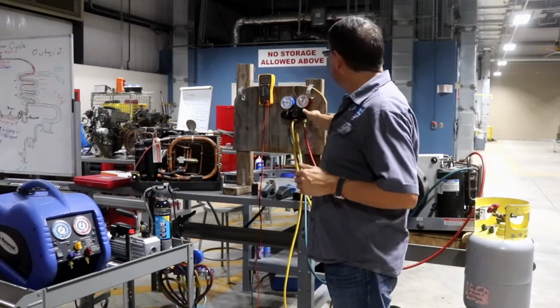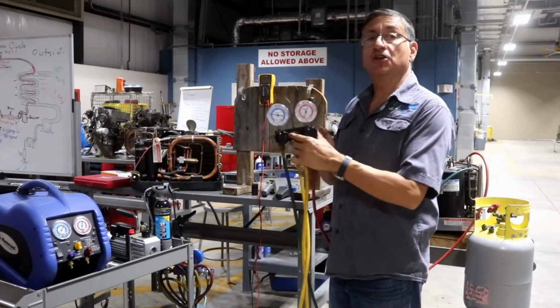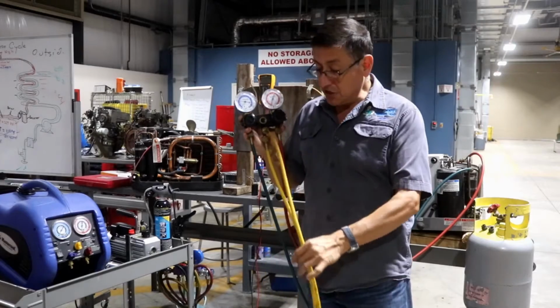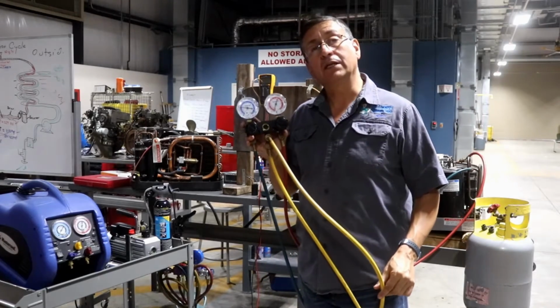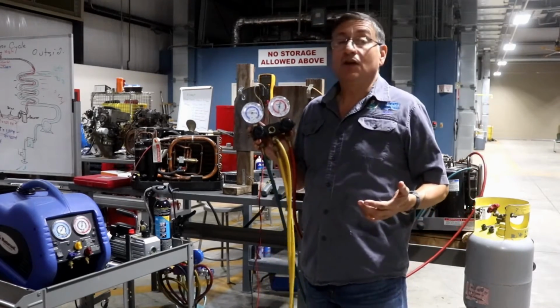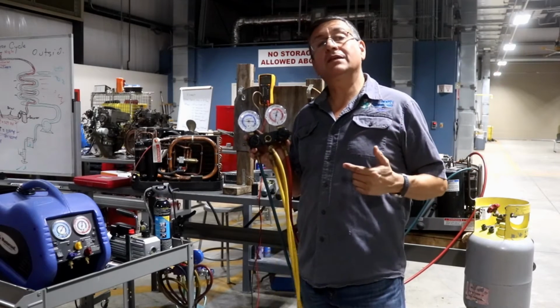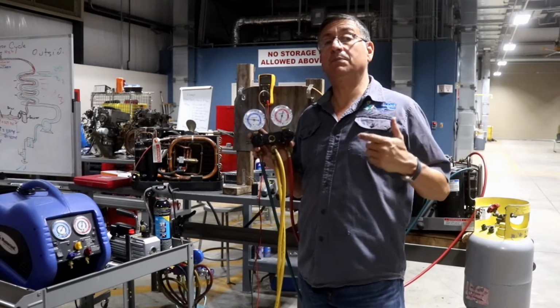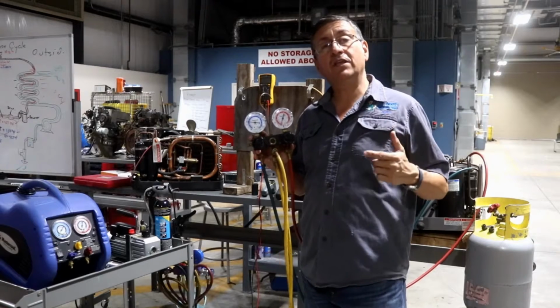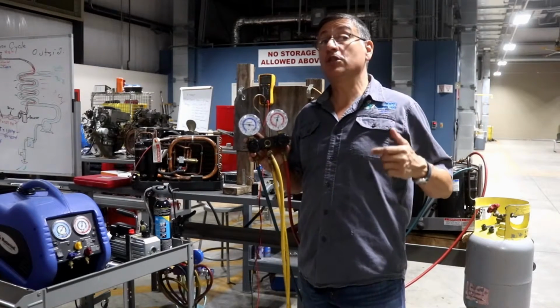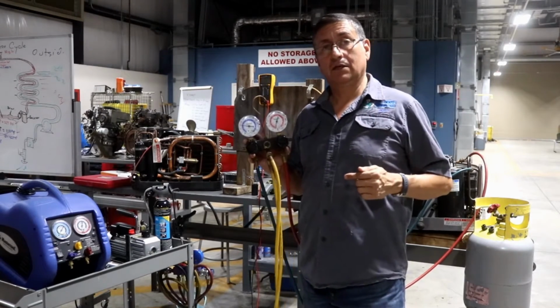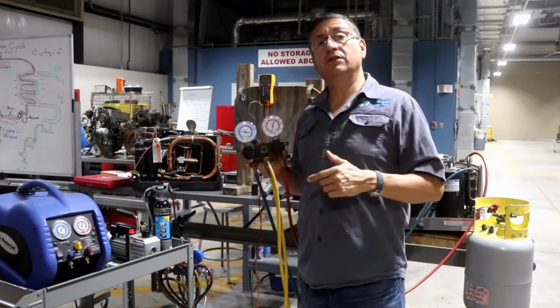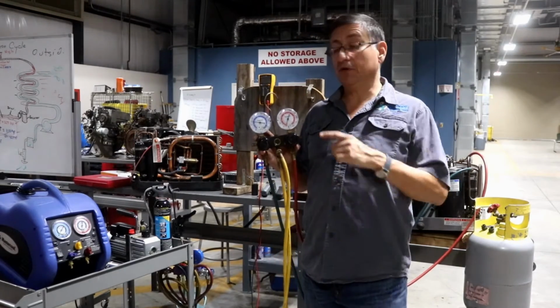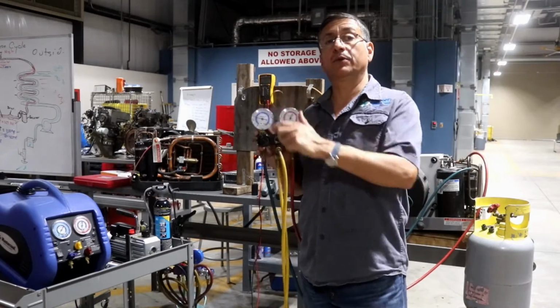One of them is the set of gauges. The set of gauges is very, very important because with the gauges we know the pressure in the system. Remember, in a previous episode I explained that the refrigeration cycle is based on the pressure of the refrigerant. The pressure in the low pressure side of the system and the pressure in the high pressure side. High pressure side and low pressure side.